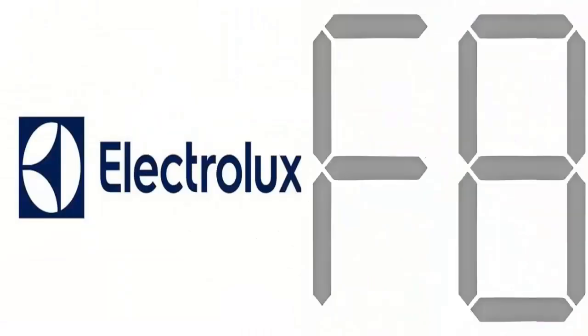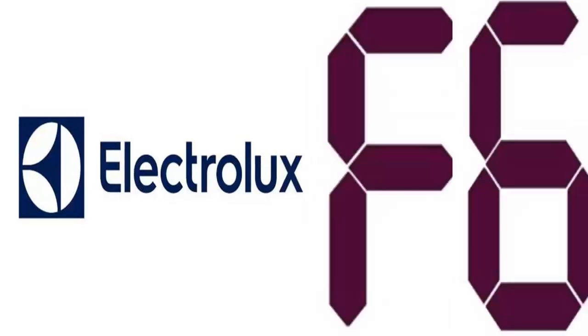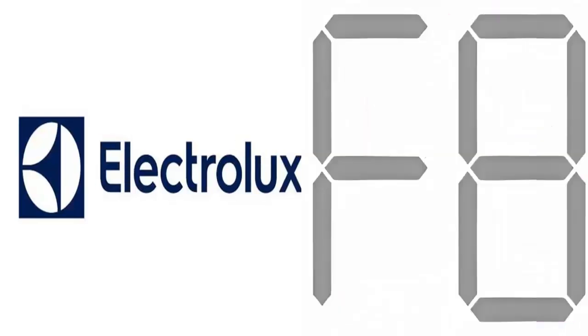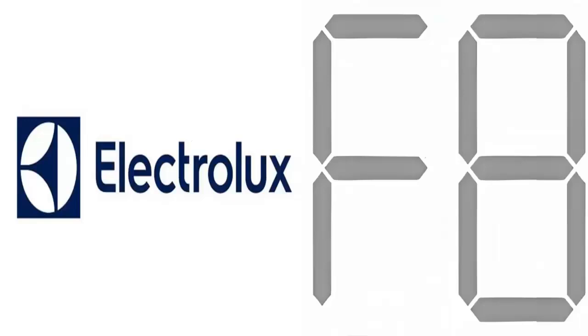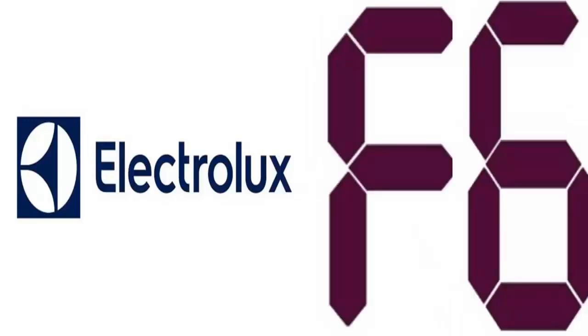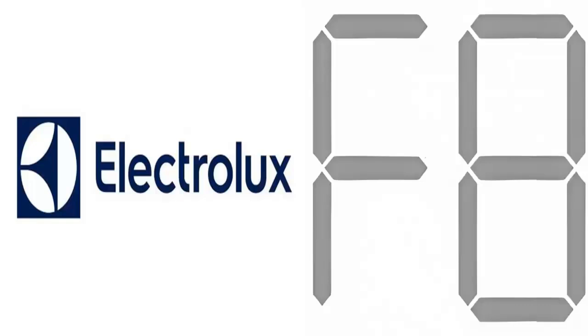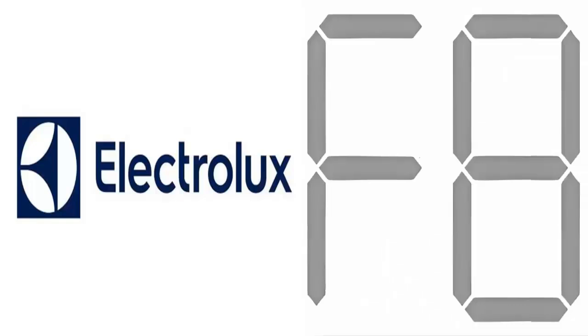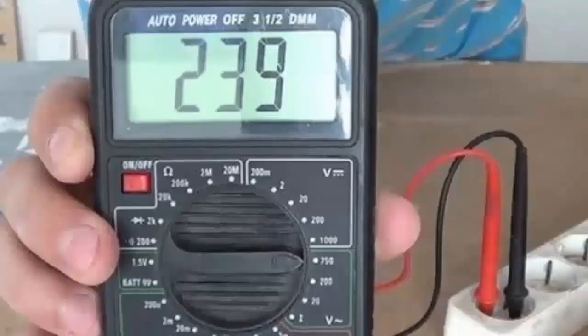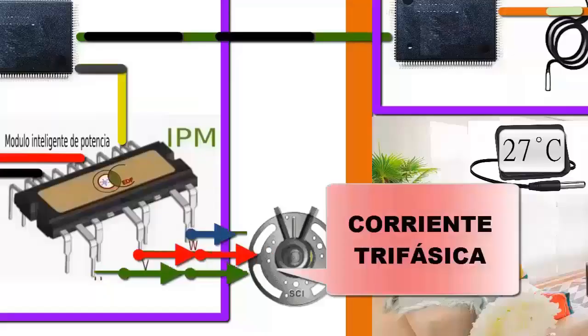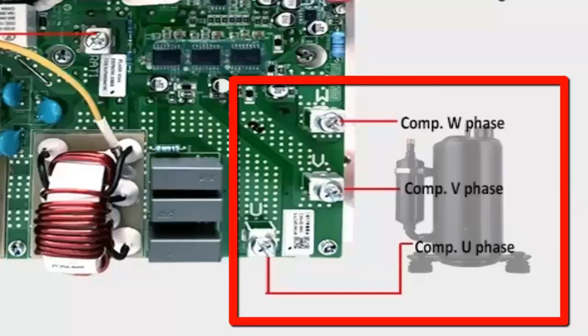The error codes F6 and F8 indicate an overload limit and overcurrent, respectively. These codes are generated when there is an issue with the compressor's operation or functionality. To resolve this, follow these steps. First, verify the correct voltage supply from the external source. Additionally, check the connections from the external board to the compressor.